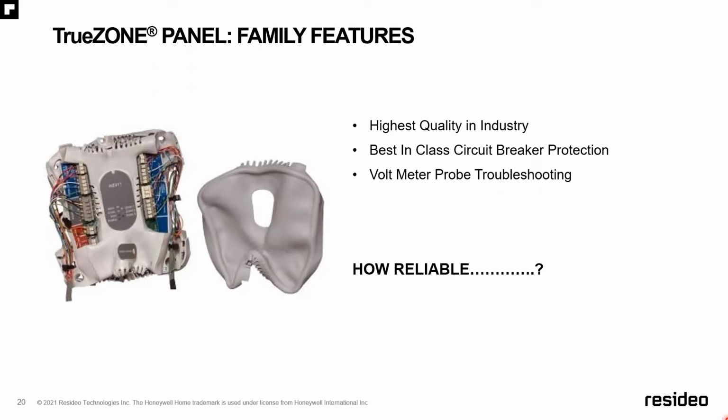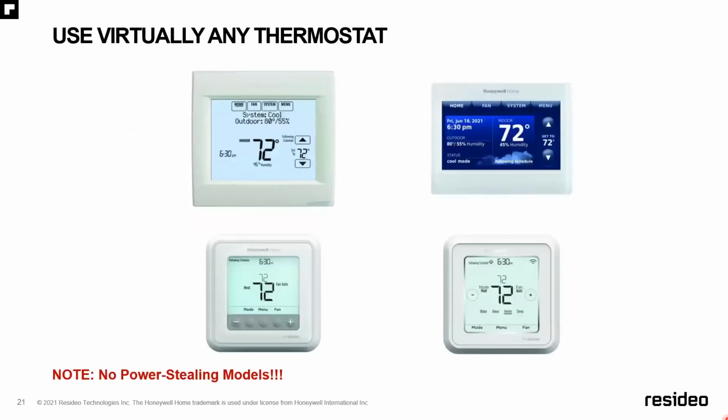And so we can easily go up to temperatures of 160 degrees, but this one obviously got exposed to more than that. But believe it or not, this one was still operating. So when they say looks can be deceiving, it applies to even zoning panels sometimes.